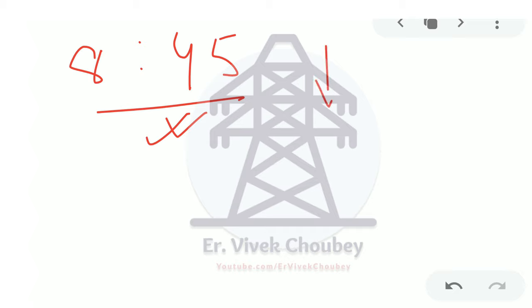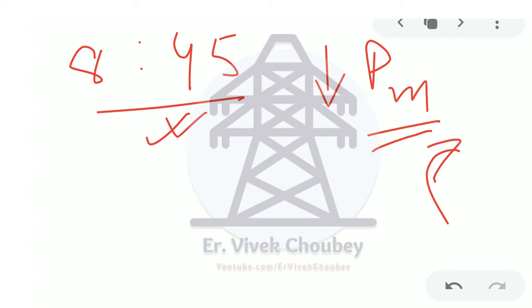Eventually, that resulted in a decrease in the mechanical power input. And as the mechanical power input decreased, keep in mind that at that time the electromagnetic torque was high. Why? Because the demand was not low at that time. The demand got low at 9 p.m. But they took action and began to decrease this mechanical power from 8:45 p.m. Now you will ask, if they began to decrease the mechanical power input or the steam input, how was the demand met at that time?